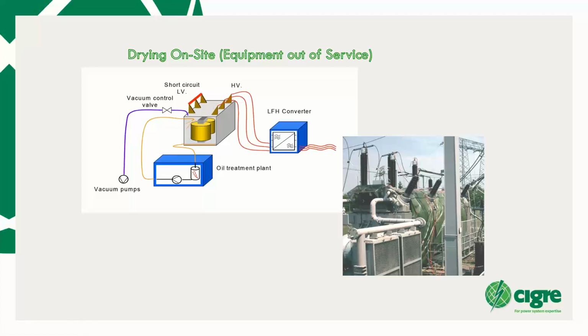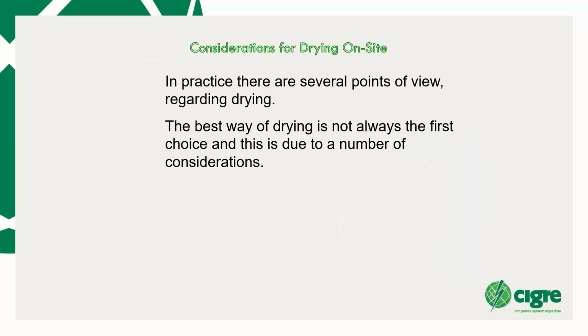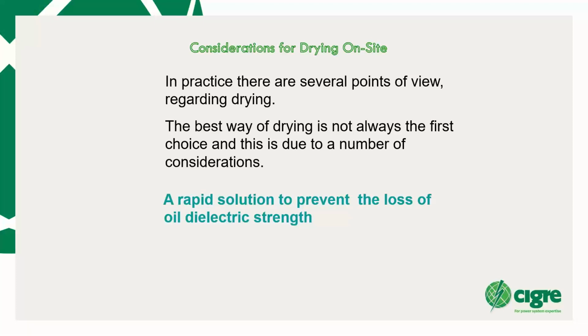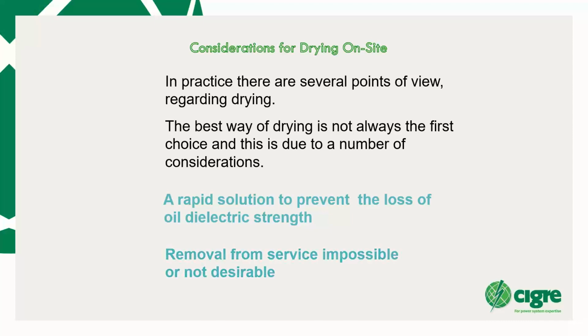The transformer must be, of course, not only low frequency heated, as that is not effective enough. You need hot oil spraying in order to have a really good drying result. Of course, there are different ways of dealing with drying, but it is not always possible to do that. The first thing to be done is actually to prevent the loss of the dielectric strength. And there are cases when removal from service is impossible because of logistical reasons, or because it is not economical enough, or whatever. In this case, of course, there are other methods which can be employed.